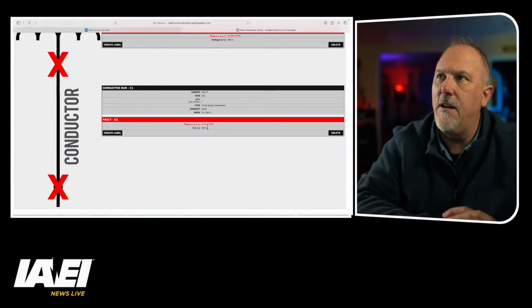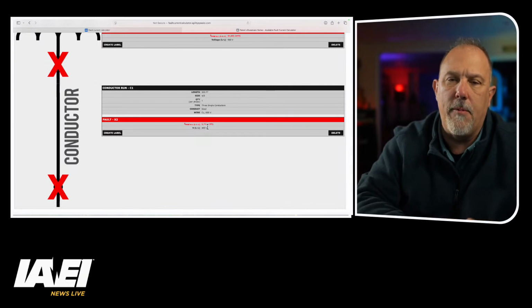So if you had 500 feet of 4-aught on the secondary of that, which probably would not be enough from an ampacity perspective, but that's not the point. So you have a tool. You have a fundamental understanding of what the tool is doing. It's taking your power system, converting it to impedances, and calculating a fault current based upon Ohm's law. And then we're going to take that number and compare it against the interrupting ratings of circuit breakers and fuses and short circuit current ratings of equipment.